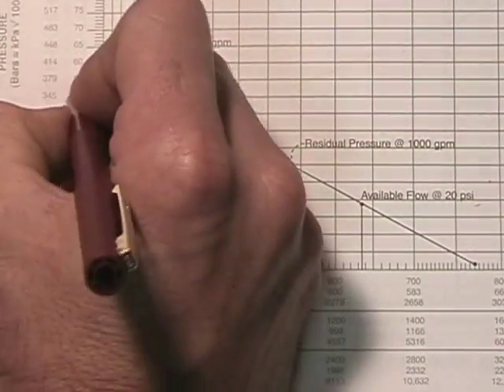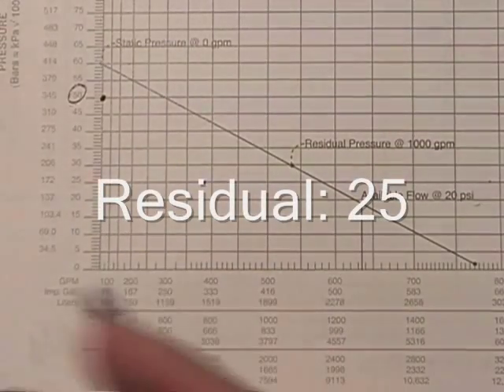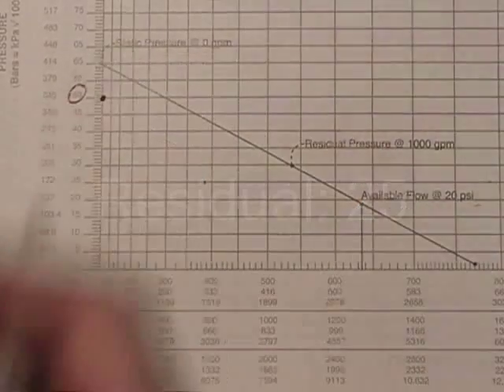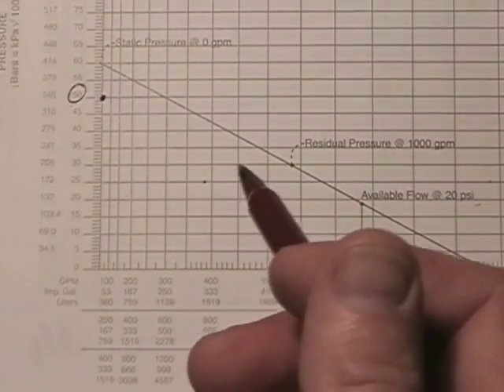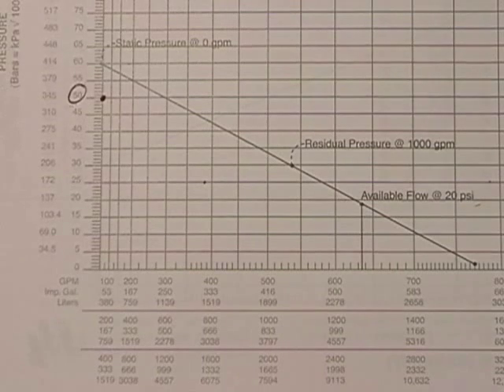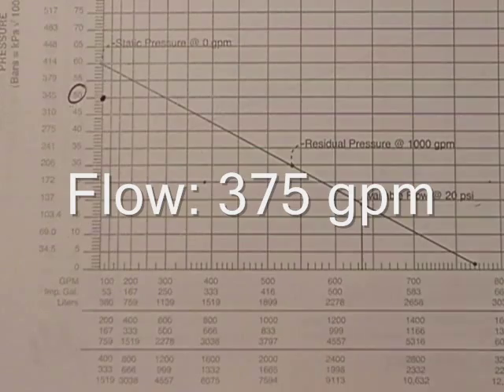The next step is we're going to take our residual, and we'll say our residual is 25. So after we were flowing a hydrant, our test hydrant dropped from 50 to 25. We're going to have to calculate our water flow, either using a chart or using the calculation that we already learned, to find out how many gallons per minute is coming out of that hydrant. But let's say the results of our test showed that it wasn't a very good hydrant, and it was only flowing 375 gallons per minute.